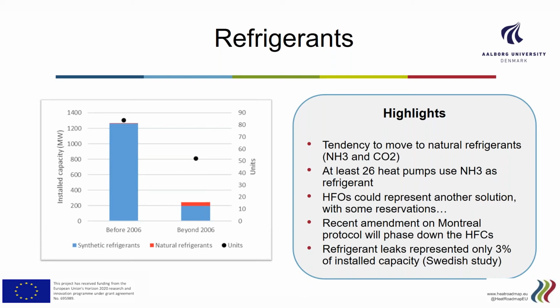It can work at temperatures up to 90 degrees Celsius, such as the Drammen heat pump plant in Norway, and can have a COP of 3 or even over 3 quite easily. Its efficiency is comparable with one of the synthetic refrigerants analyzed in the survey, but it's also moderately flammable and toxic, so it requires some specific safety precautions. In the survey, we managed to identify 26 units using this refrigerant with a total capacity of 51 megawatts thermal, with some of the oldest units in the survey operating in Lausanne in Switzerland since 1986.